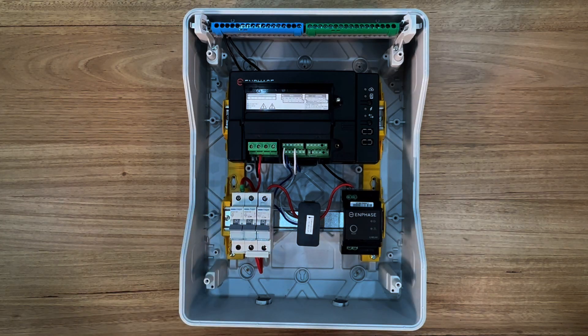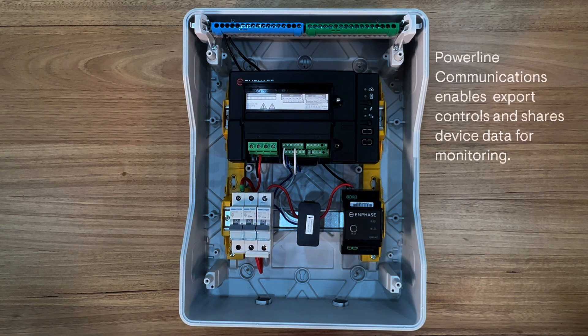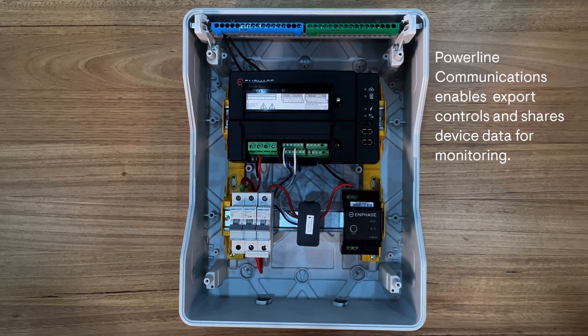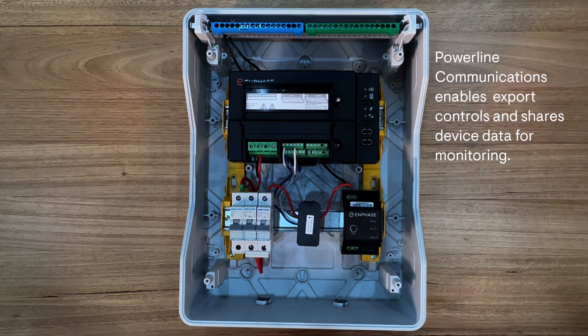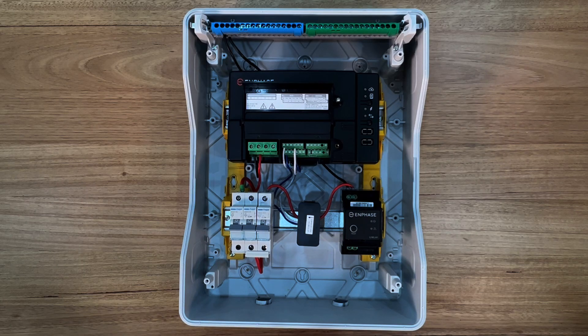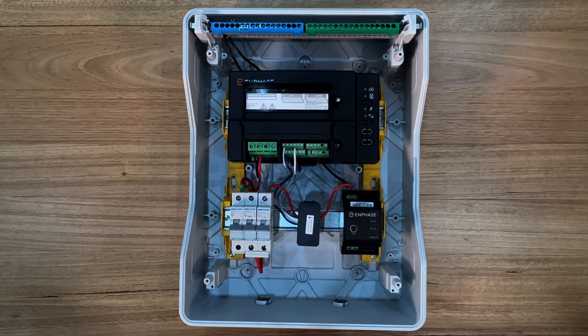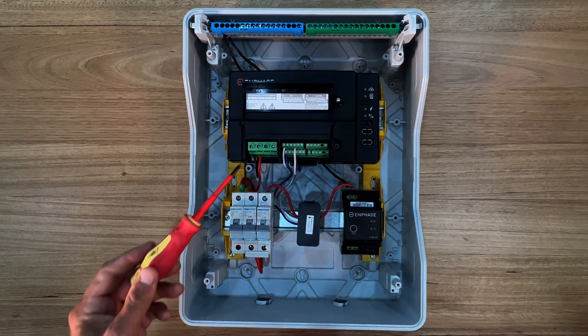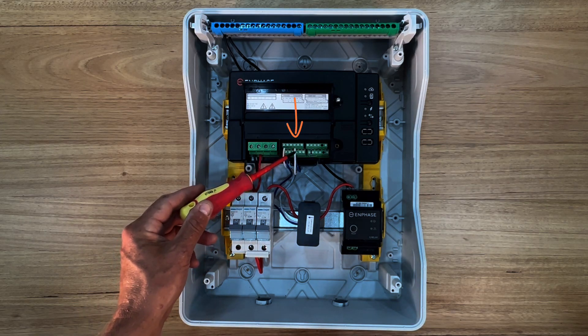This IQ gateway communicates by AC power line through the circuit wiring. It enables communication and control to the Q relays and microinverters. For consumption monitoring and export control you will also install a consumption CT and connect it to the L1 terminals here.